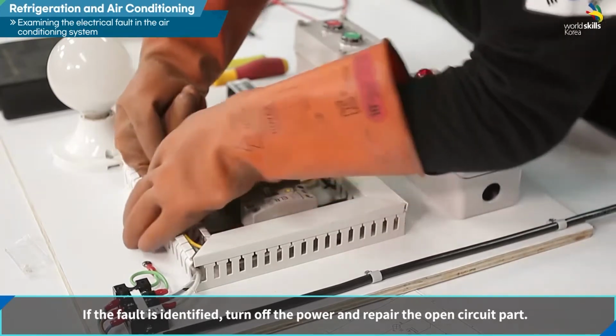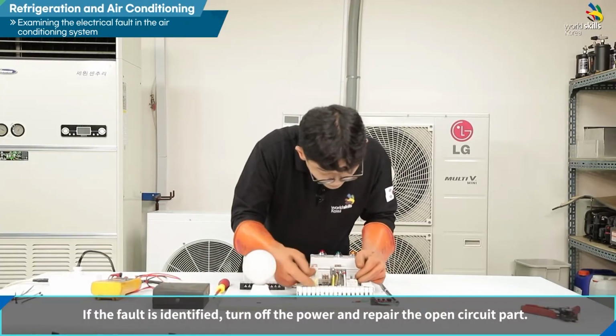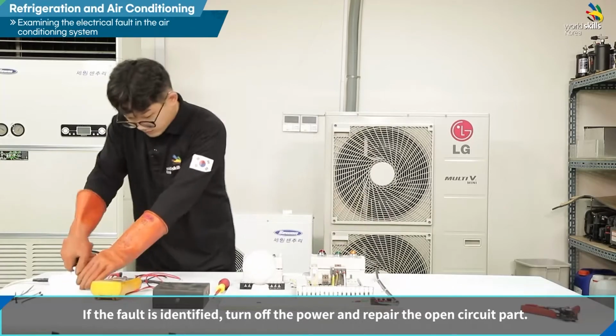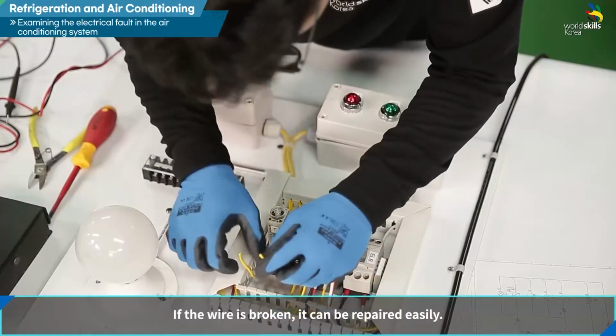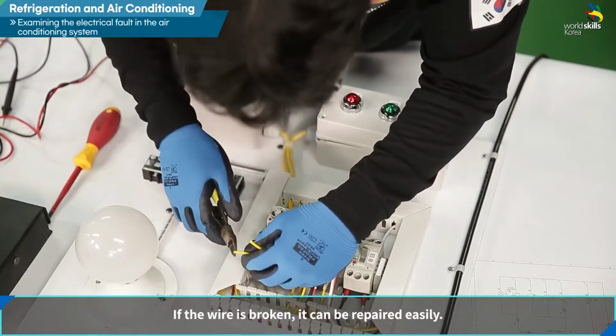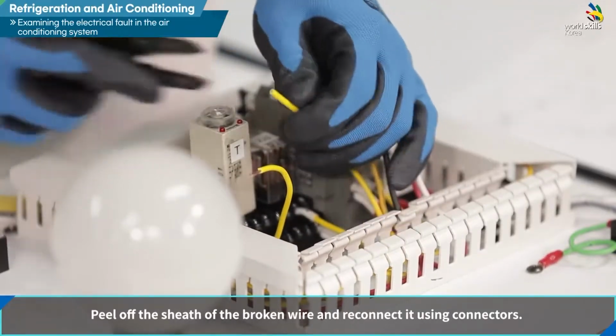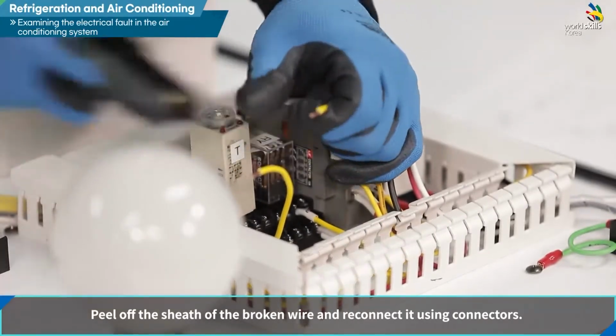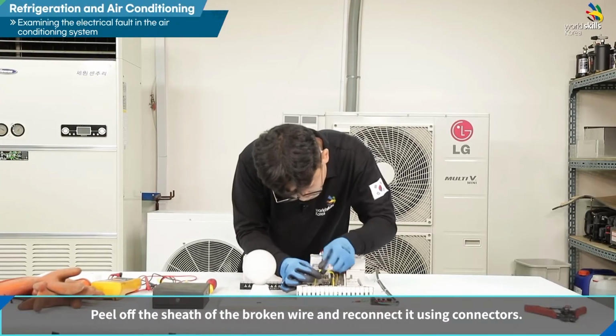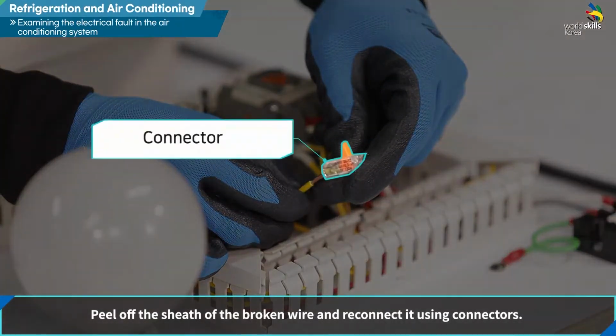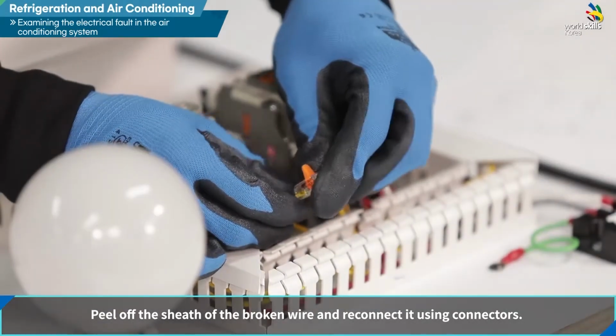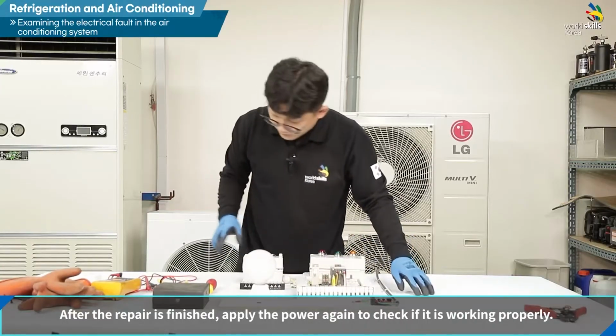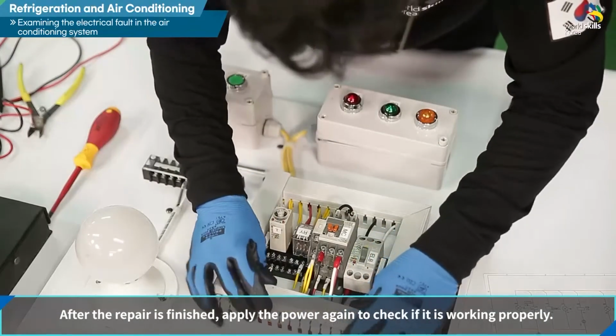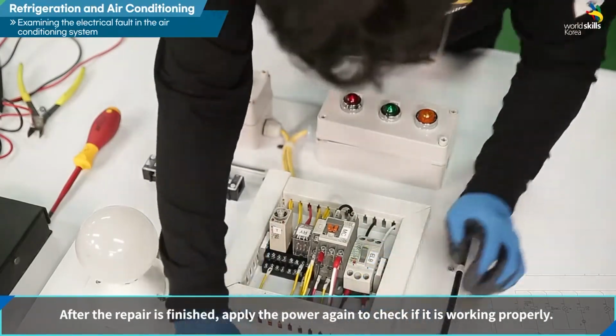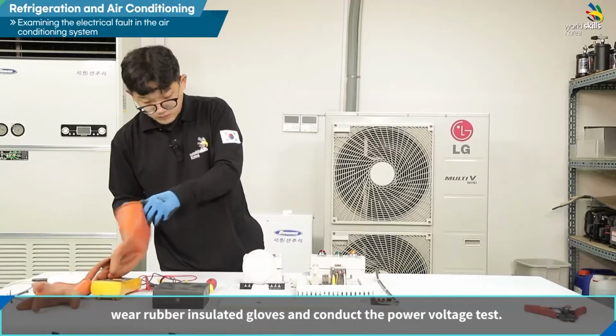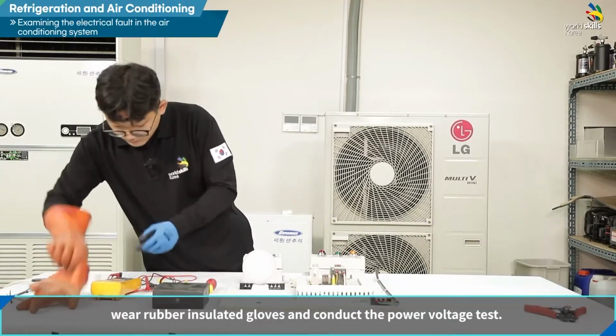If the fault is identified, turn off the power and repair the open circuit part. If the wire is broken, it can be repaired easily. Peel off the sheath of the broken wire and reconnect it using connectors. After the repair is finished, apply the power again to check if it is working properly. Before supplying power, wear rubber insulated gloves and conduct the power voltage test.